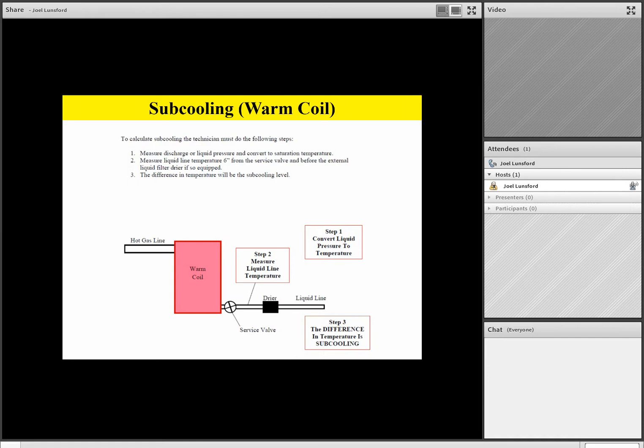So again, normal subcooling in the cooling mode of operation on a heat pump with properly sized equipment should be about 10 to 15 degrees of subcooling in the cooling mode. But in the heating mode of operation, normal subcooling can go anywhere between 15 to 25 degrees because of the physical size differences of the coils. So in the heating mode of operation, we're going to see much higher subcooling levels. That's normal. So subcooling always tells us the condition of the warm coil.